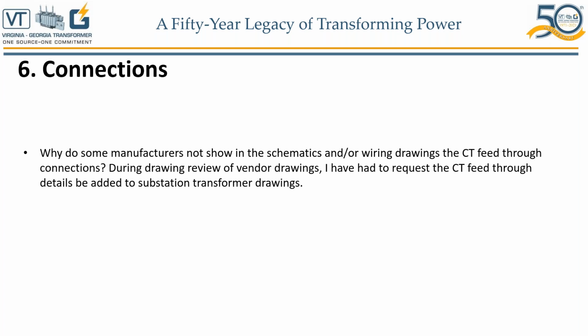I agree with the submitter, it should be submitted. However, why they don't submit it, maybe it's because they don't want to have confusion, because the feed throughs will have, say, sometimes 30, 36 pins on it. However, the terminal blocks will have only 6 per CT. To avoid the confusion, that's probably why they don't do that. That's my assumption.